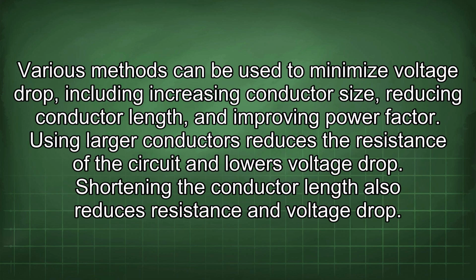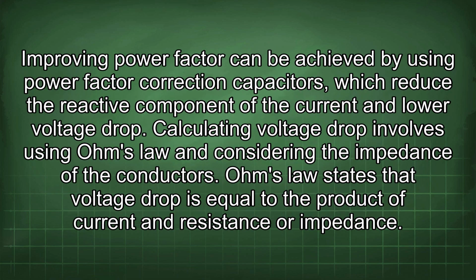Various methods can be used to minimize voltage drop, including increasing conductor size, reducing conductor length, and improving power factor. Using larger conductors reduces the resistance of the circuit and lowers voltage drop. Shortening the conductor length also reduces resistance and voltage drop.